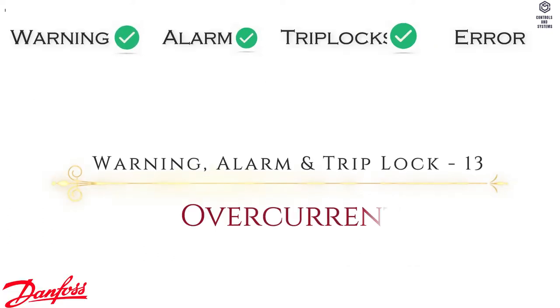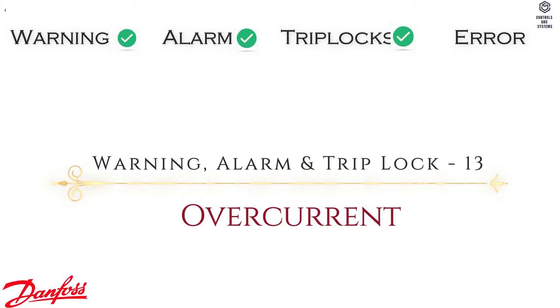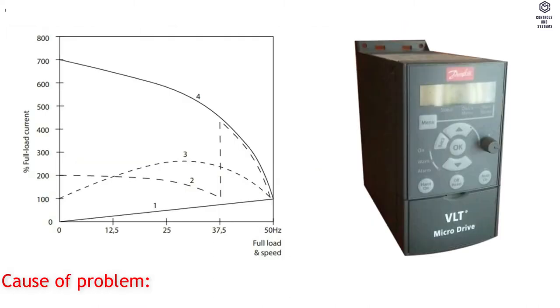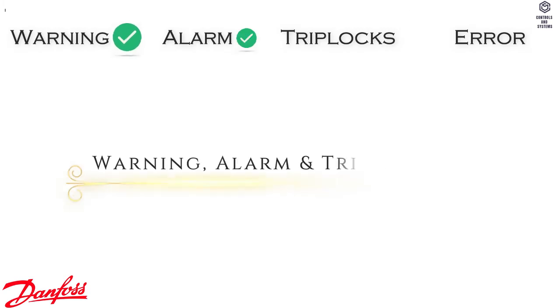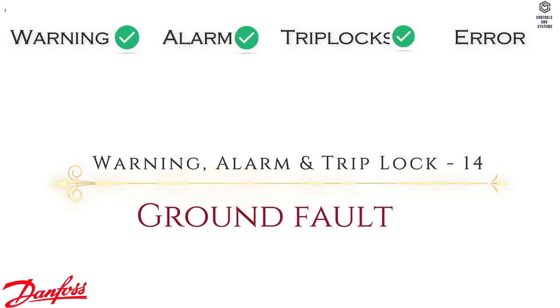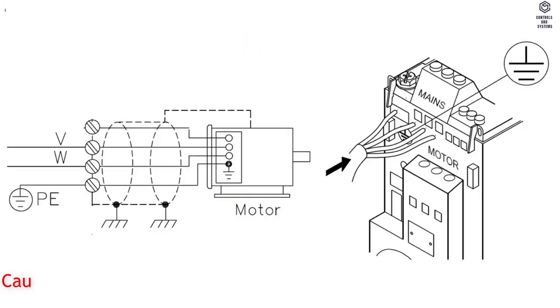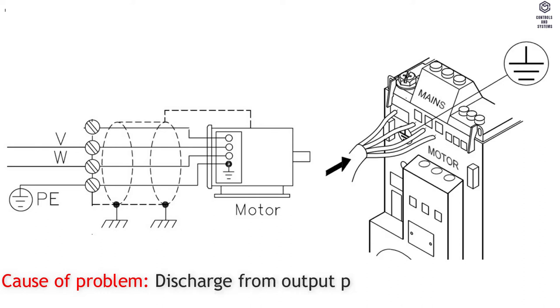Warning, Alarm and Trip Lock 13: Overcurrent. Cause of Problem — inverter peak current limit is exceeded. Warning, Alarm and Trip Lock 14: Ground Fault. Cause of Problem — discharge from output phases to ground.